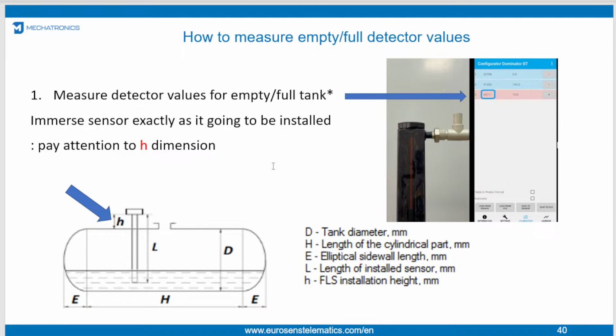And pay attention to how it's going to be installed. On big fuel storage, typically you install the sensor in the neck, and the neck level is a bit higher than the tank surface. That means when your tank is full, your sensor is not immersed fully into fuel. So you need to dip the sensor during calibration at the same level, leaving part of the sensor outside the fuel. After dipping, you note the full value, and then remove the sensor and note the empty value.